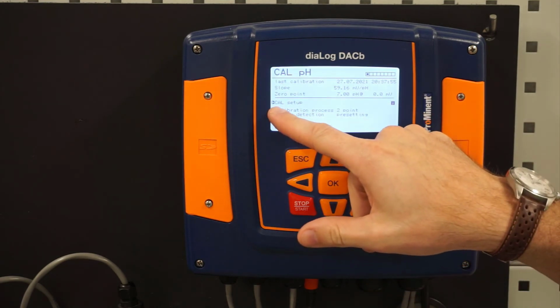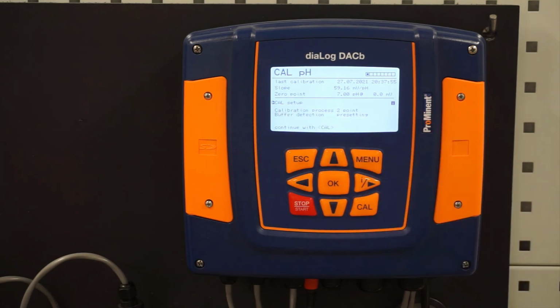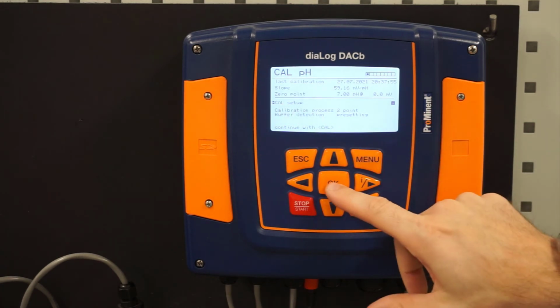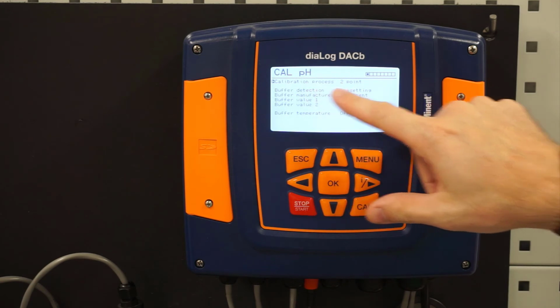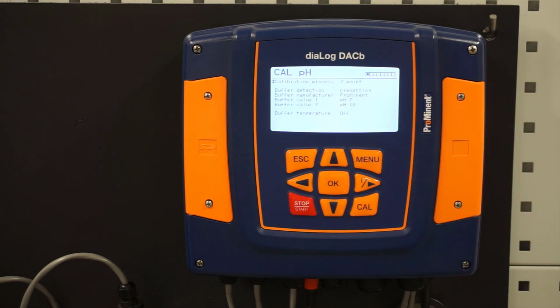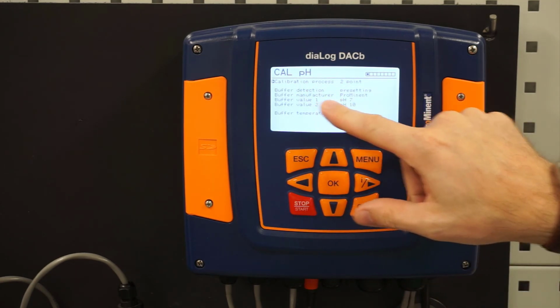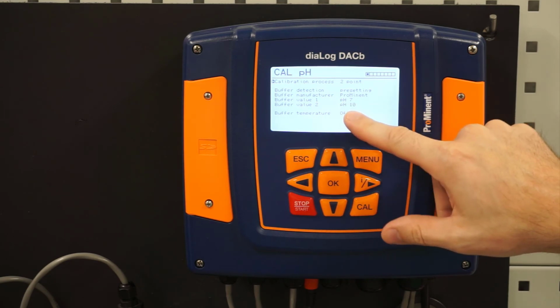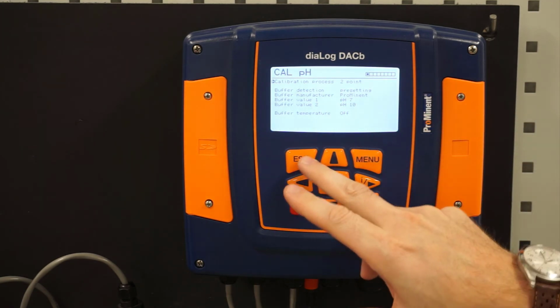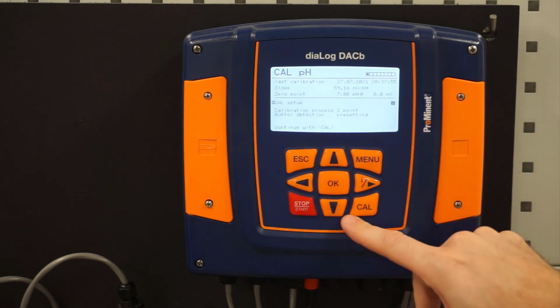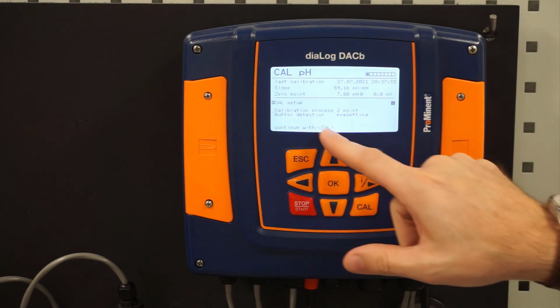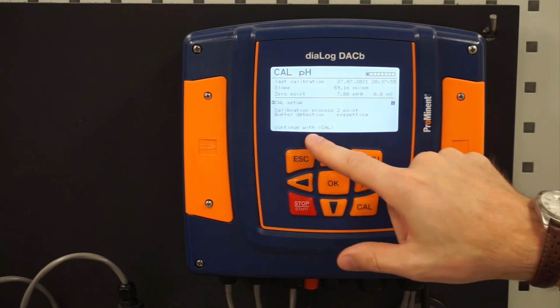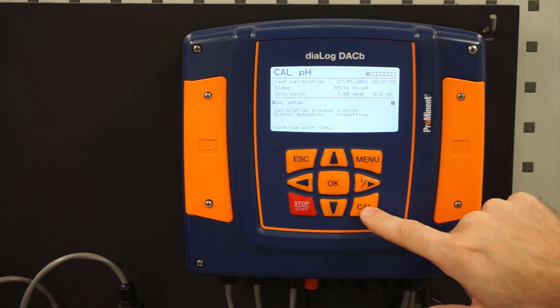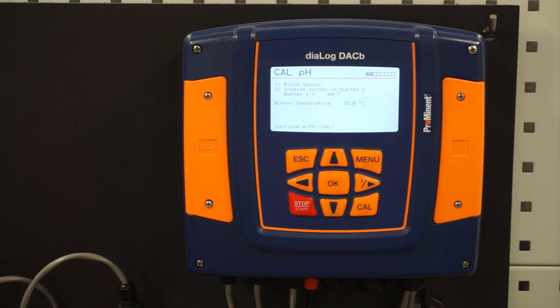First thing, you can see our cursor is next to cal setup. So we can go in there and see what the setup is. Right now we're set up to do a 2-point, which is what we're going to do. And we're going to do a buffer of 7 and 10. So our setup is good. We can escape. Once we know our calibration setup is good, down here it says continue with cal. So we're going to hit the calibrate button. And now it's going to tell us what our next steps are.